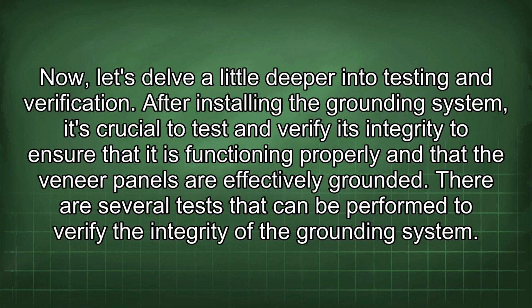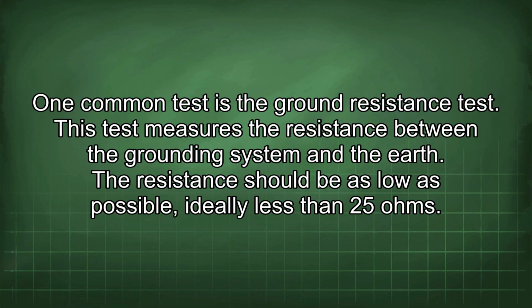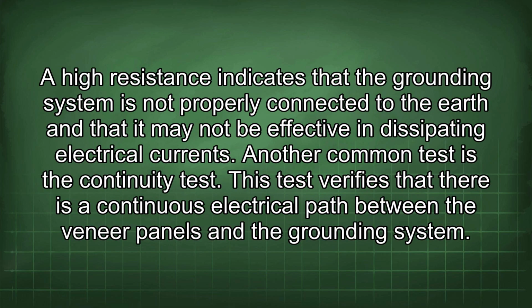Now let's delve a little deeper into testing and verification. After installing the grounding system, it's crucial to test and verify its integrity to ensure that it is functioning properly and that the veneer panels are effectively grounded. There are several tests that can be performed to verify the integrity of the grounding system. One common test is the ground resistance test. This test measures the resistance between the grounding system and the earth. The resistance should be as low as possible, ideally less than 25 ohms. A higher resistance indicates that the grounding system is not properly connected to the earth and that it may not be effective in dissipating electrical currents.